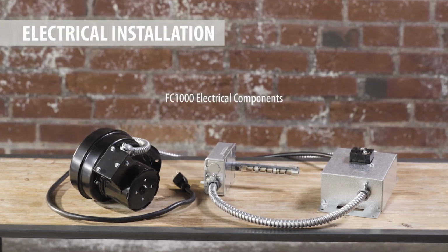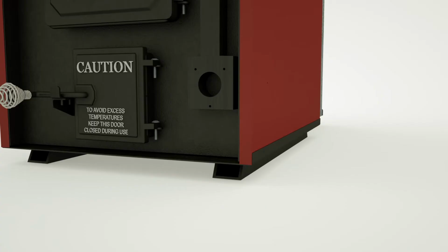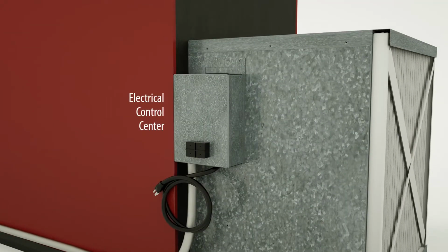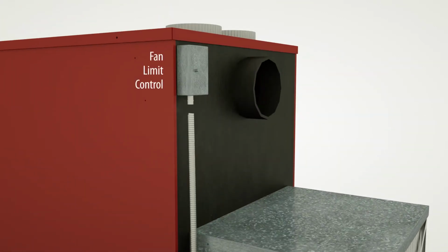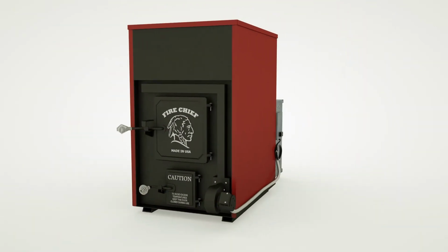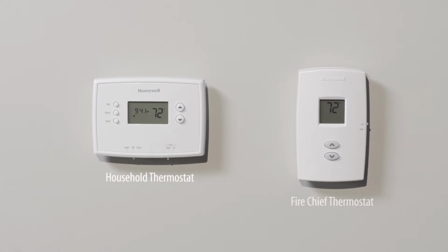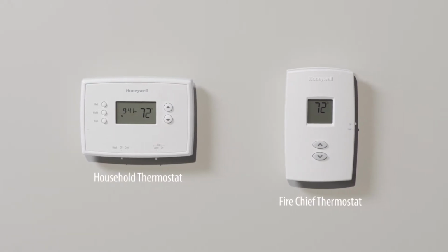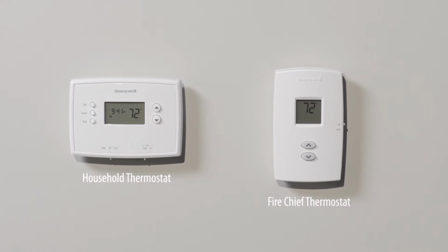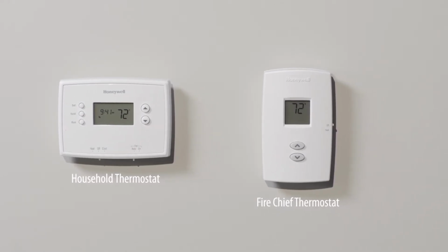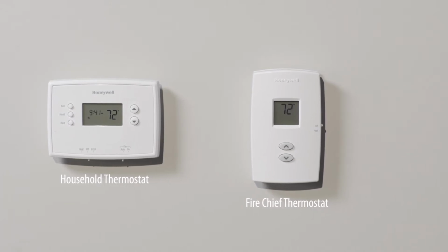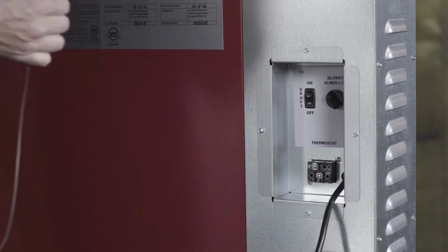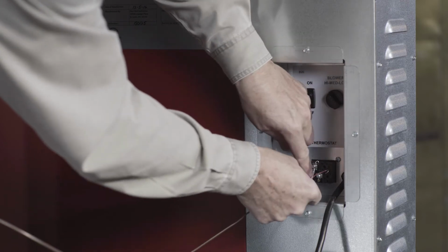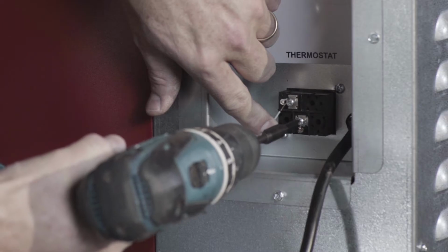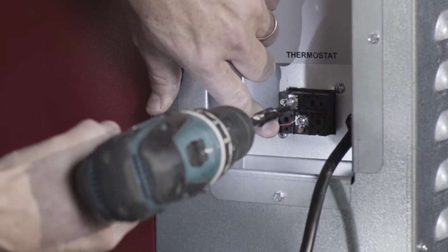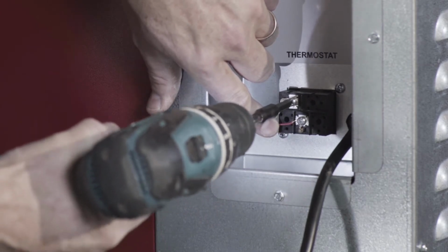If you have purchased the FC1000 model, you will be required to install the draft blower, electrical control center, and fan limit control. On all other models, these components are factory installed. Every Fire Chief furnace includes a digital wall thermostat, which automatically adjusts the burn rate of your furnace based upon the desired temperature. We recommend installing your Fire Chief thermostat in the living area where the existing thermostat is located. You will need to connect the wall thermostat to the 2 terminals located on the electrical control center with standard 24-gauge 2-wire thermostat wire, which must be purchased separately.